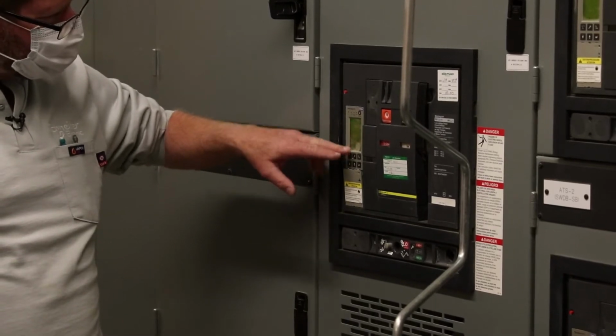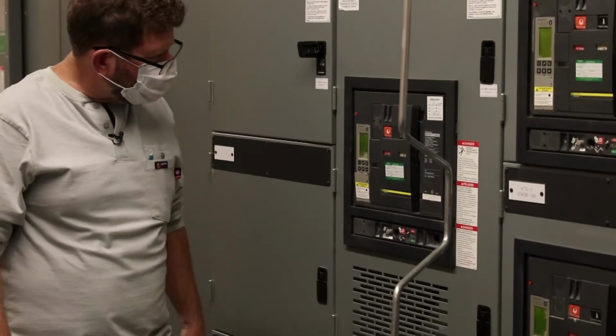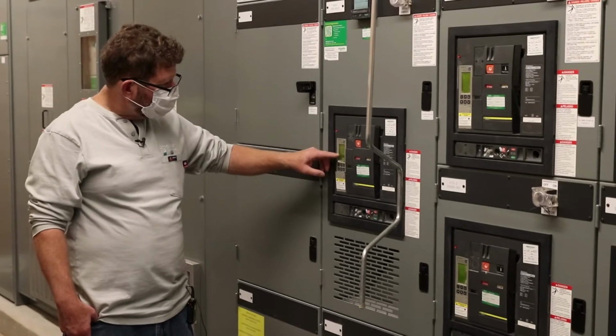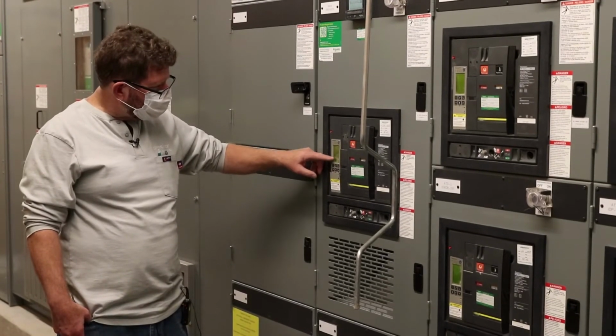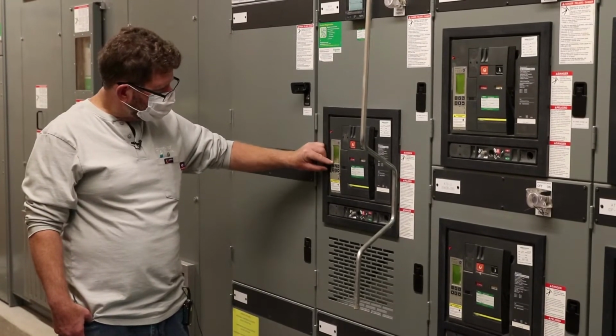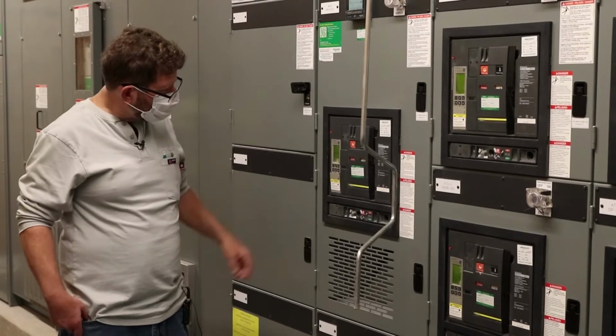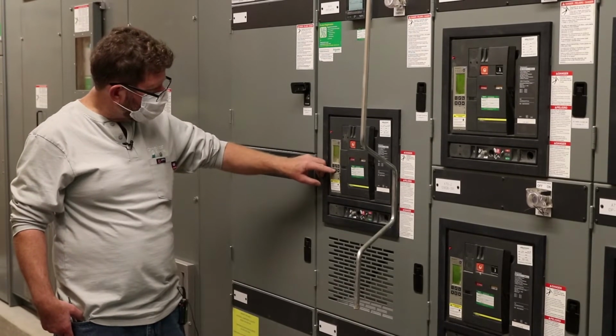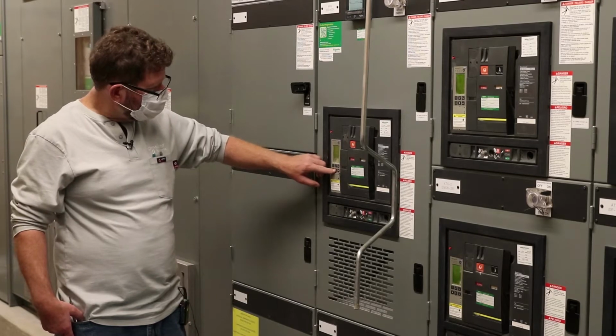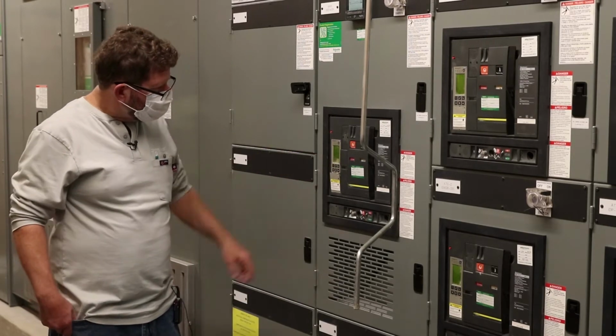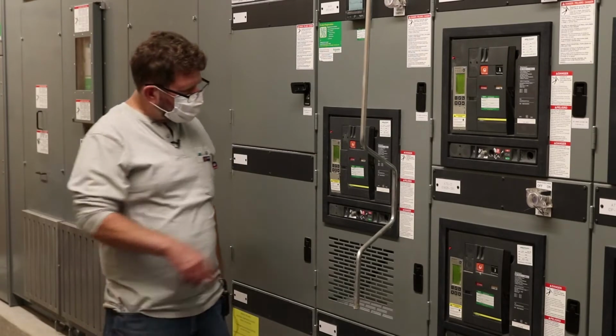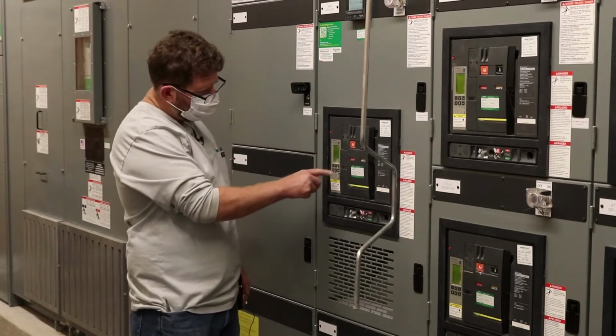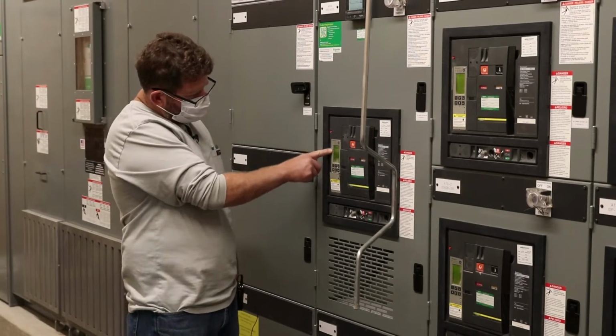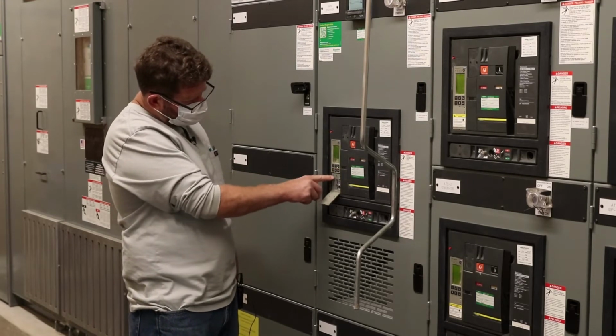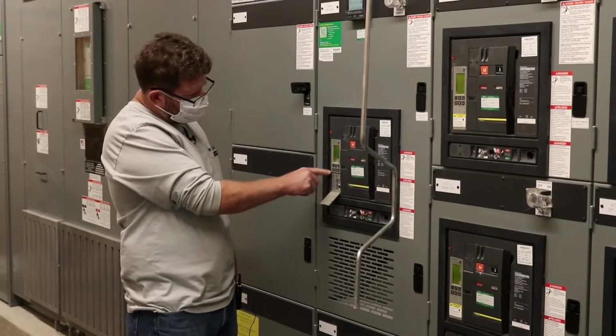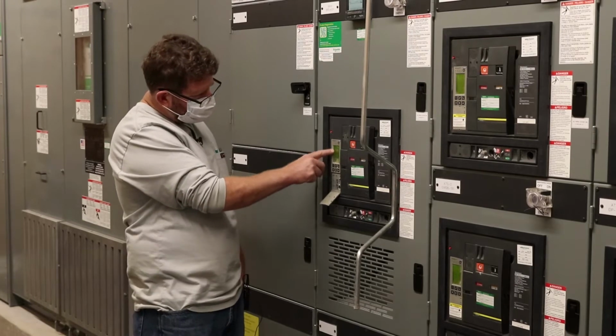Any other setup of the breaker, the trip unit, can be done through here. You have metering setup, comm setup, Micrologic setup. You can change the date time here if you needed to. Third button over here is your protection. That's showing a trip curve. You push that. Amperage protection, those values are set down here on these dials. They can be fine-tuned through this.